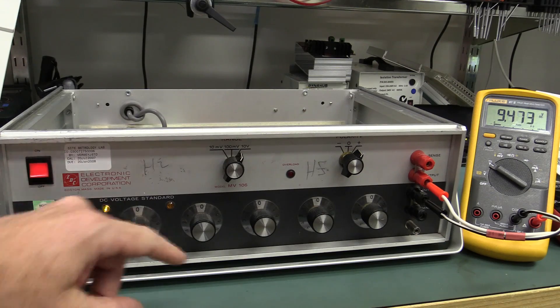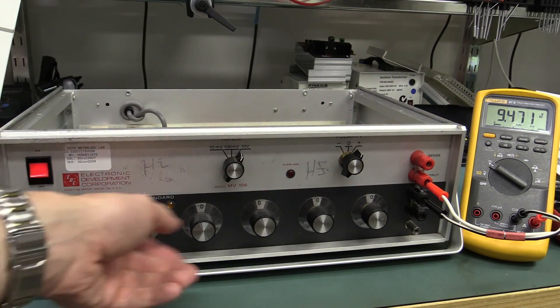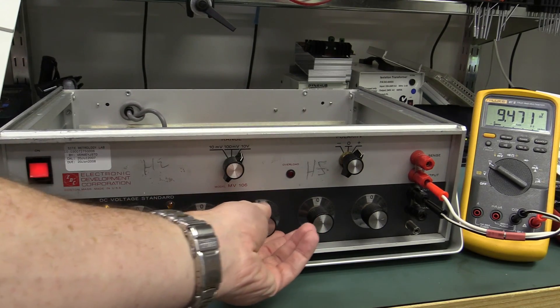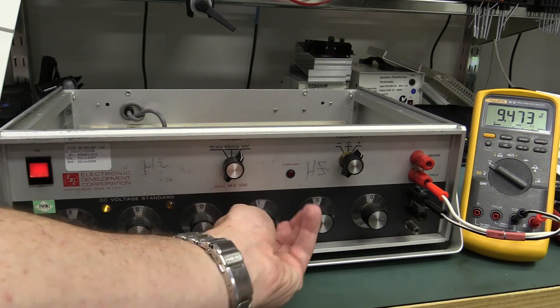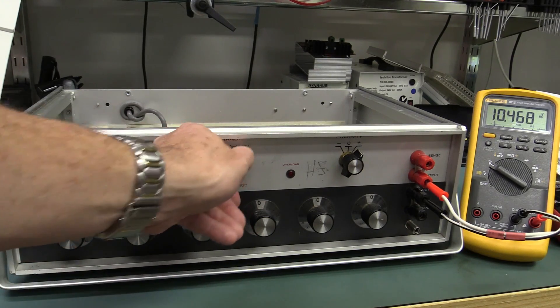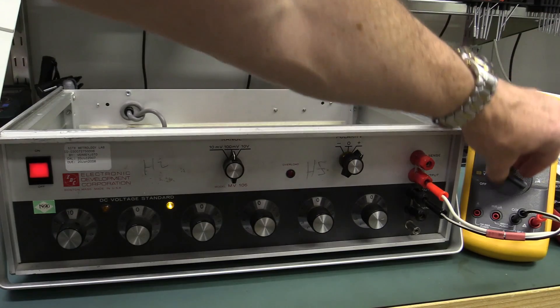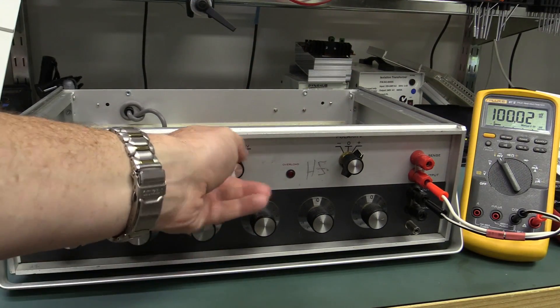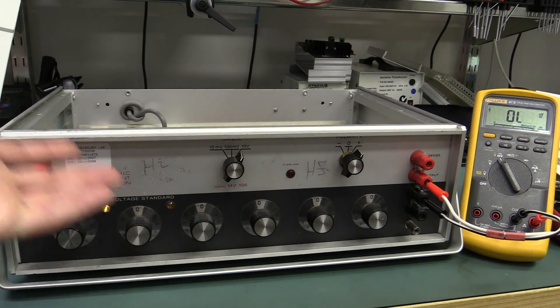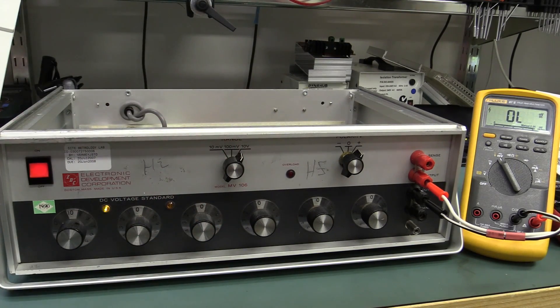And if I switch it down to 9 here, it's still 9.47. So it had all that resolution. So it seems to work, but it was out. And if I turn it down to 100 millivolts here, it's bang on, of course. And if I turn it down to 10 millivolts, it was bang on again. It was only the 10 volt range like this. So I thought, oh, no!